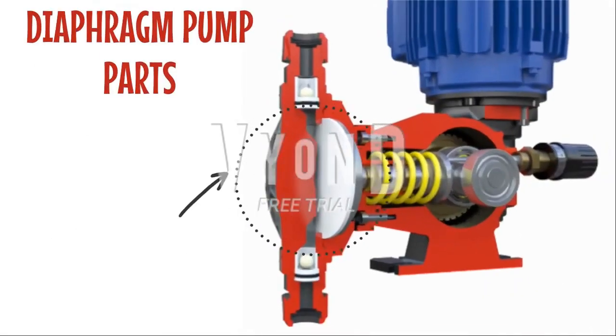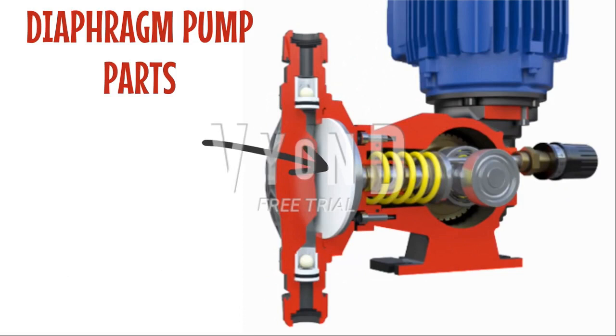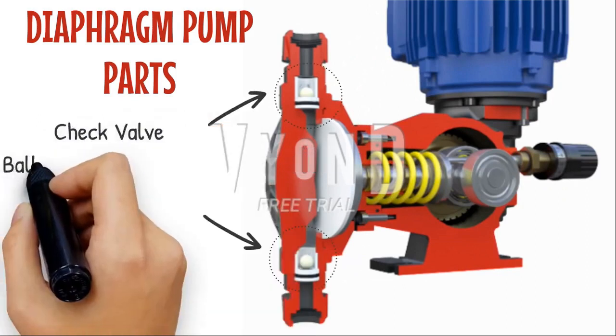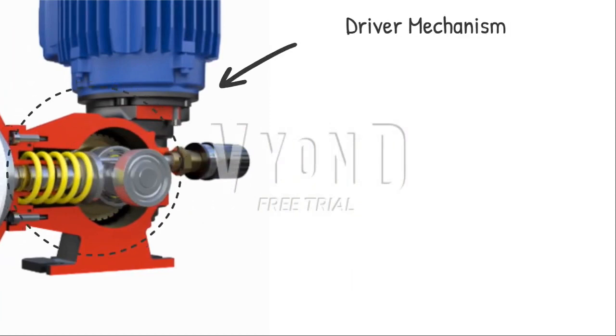A head pump body, which can be made of polyvinyl chloride, stainless steel, or polyvinylidene fluoride, makes up a diaphragm pump. The service conditions and the type of fluid to be handled decide the building materials. A flexible pulsing diaphragm, often composed of polyethylene, is another component. Two check valves, frequently made of ceramic balls and sealed with elastomer O-rings, allow flow to enter from the suction and exit from the discharge. The drive system converts the driver's rotational motion into reciprocating movement.